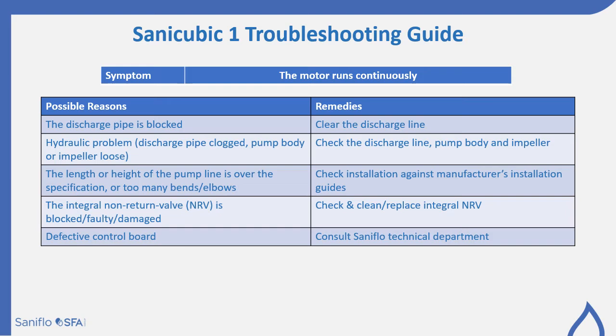If the motor is running continuously, it could be that the discharge pipe is blocked. So clear that discharge line and make sure everything's opened up. Could be a hydraulic problem, so discharge pipe clogged, the pump body or the impeller may be loose. Check all of those, the discharge line, the pump body and the impeller. It could be that the height or the length of the pump line is over our specifications or has too many bends or elbows in through there. So check the installation against the manufacturer's installation guide.